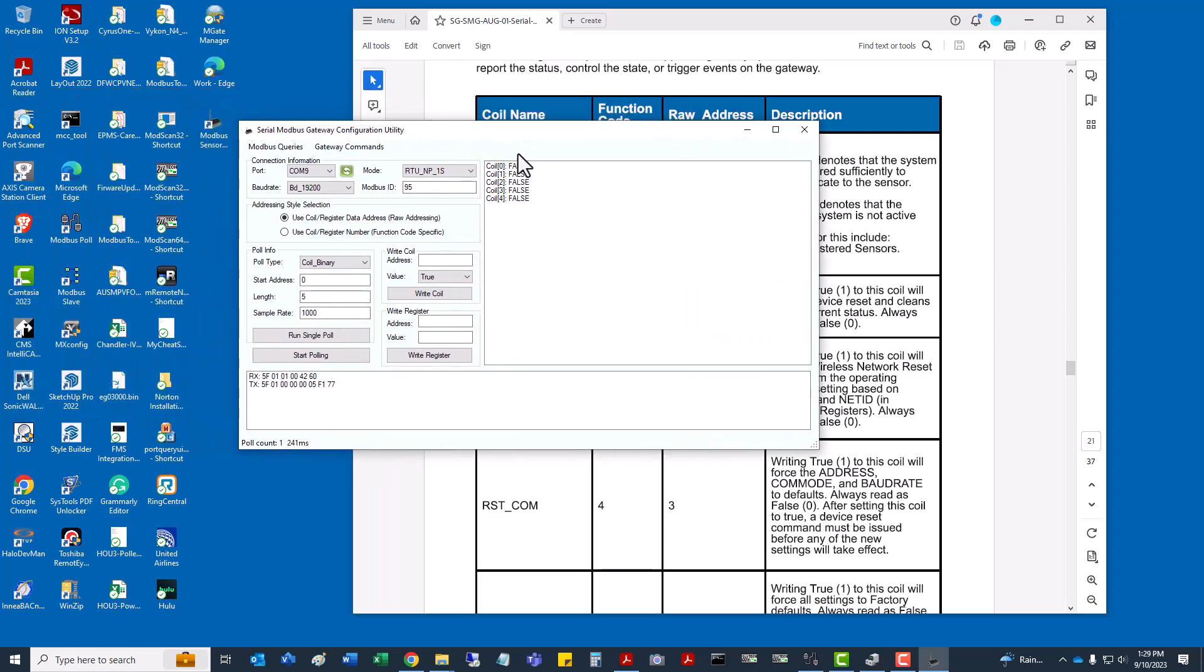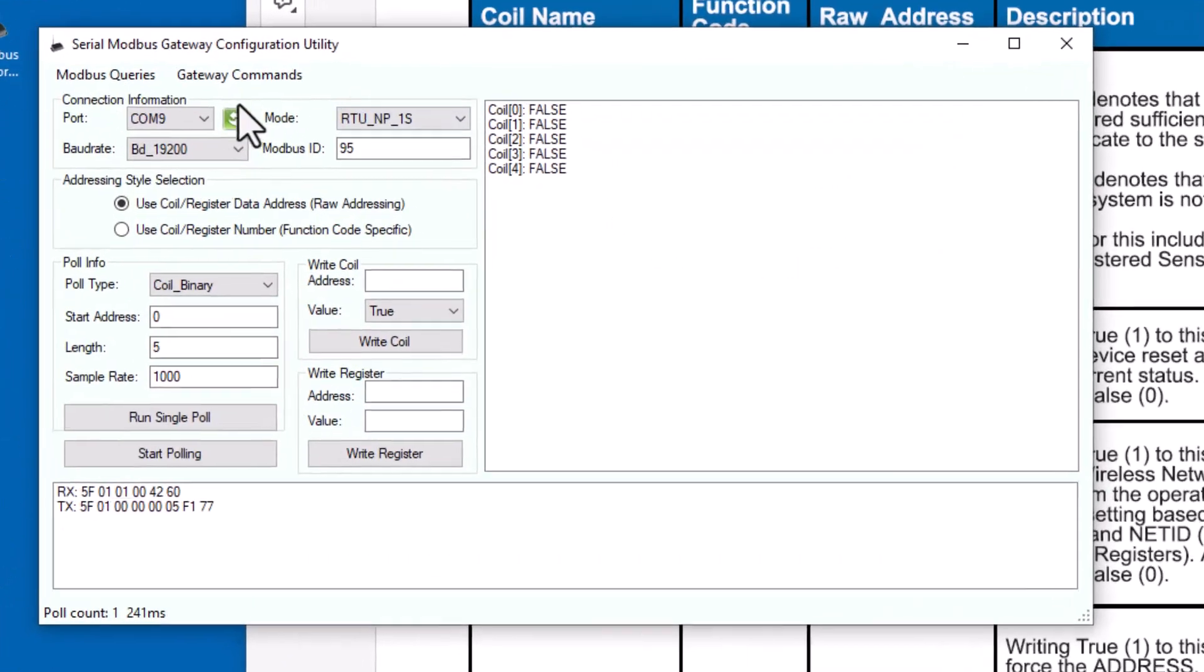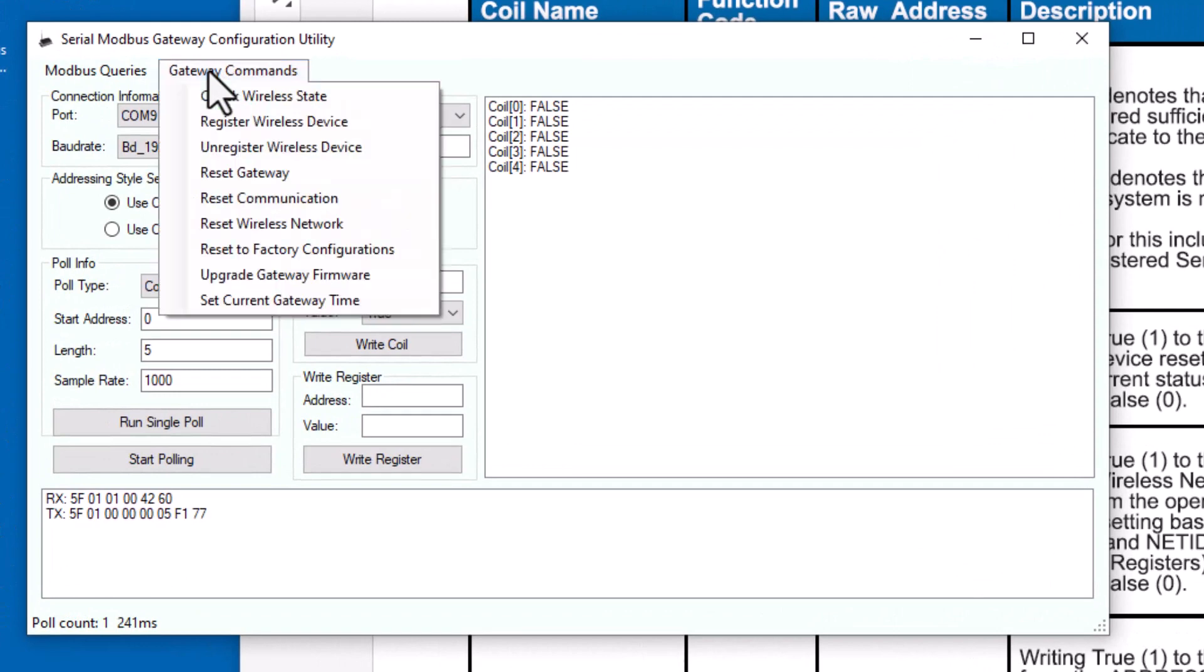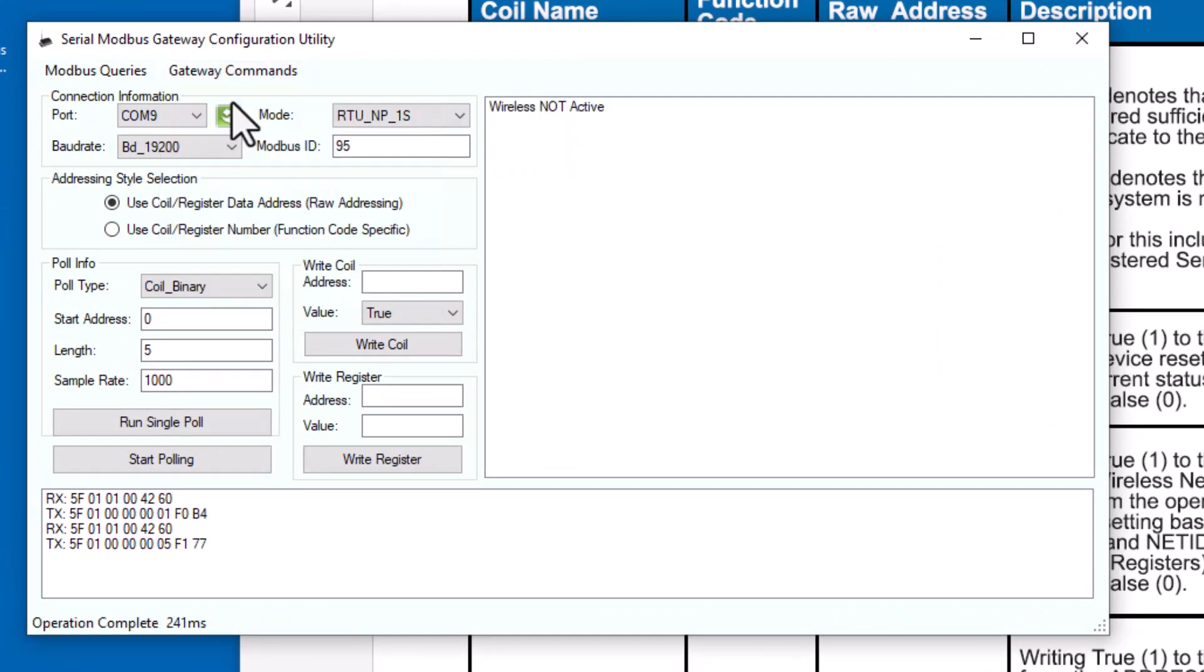The user guide, if we go down to page 18, you can see what coil represents what function. The first one, if it returns a zero or false, it denotes that the wireless sensor system is not active. If it was configured, we should see a one or a true coming back through. So that's what we're going to do with our first sensor. If we go to Gateway Commands and check the wireless state, it shows that the wireless is not active.